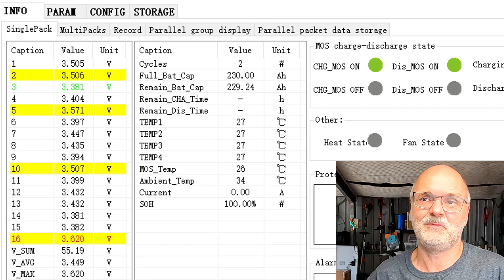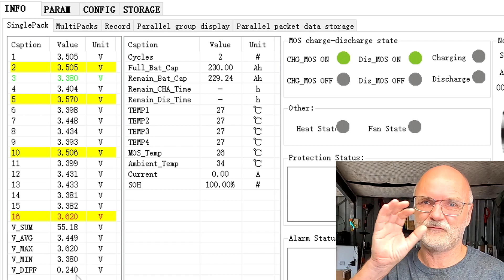You can also see the deviation is at 240 millivolts at 55.2 volts. This isn't even high voltage charging - it's just out of the knee, out of the flat area of the curve, into the steeper area.